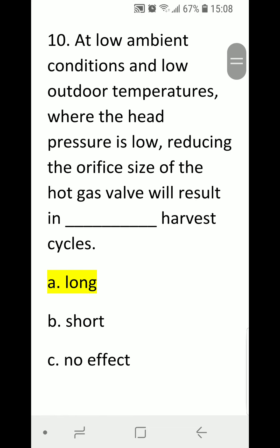Number ten: at low ambient conditions and low outdoor temperatures where the head pressure is low, reducing the orifice size of the hot gas valve will result in blank harvest cycles. A) long, B) short, C) no effect. Correct answer is A, long.